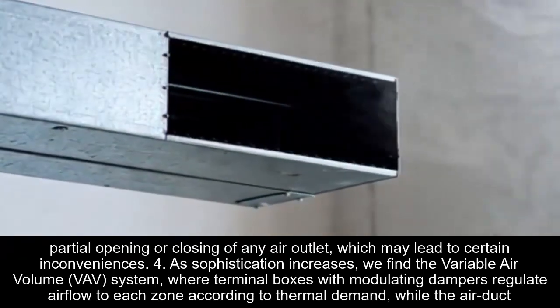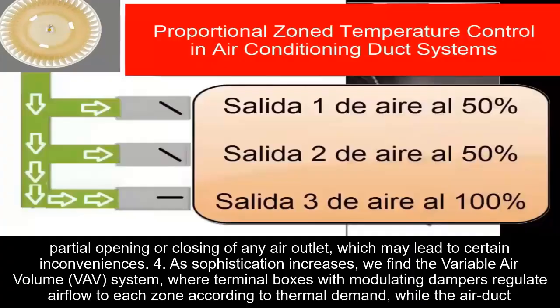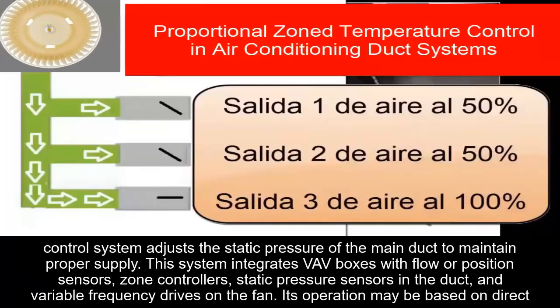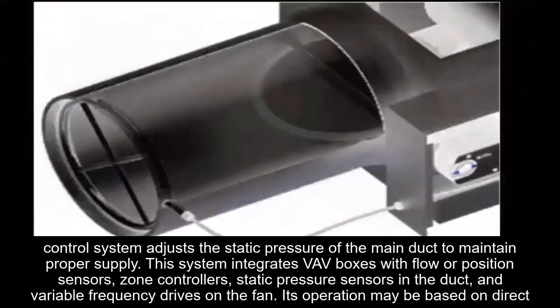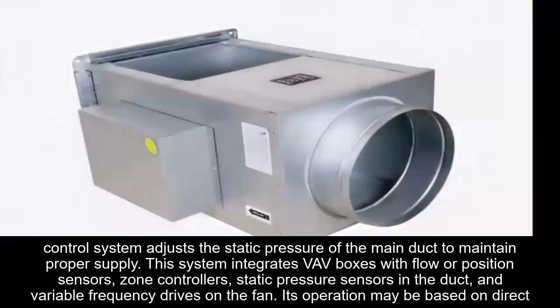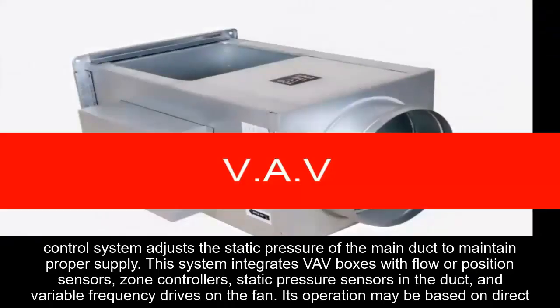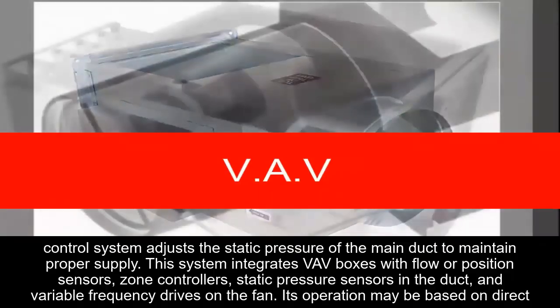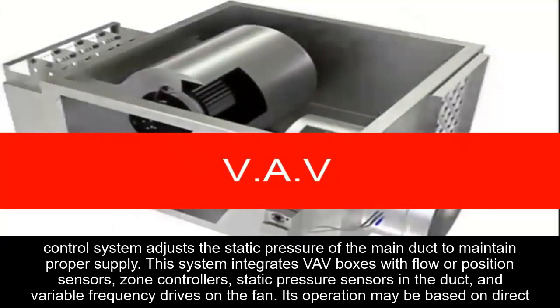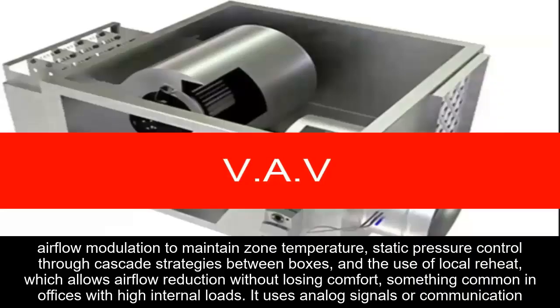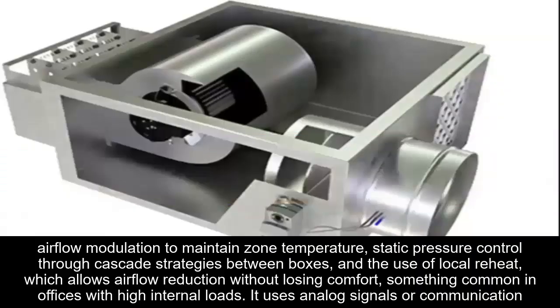As sophistication increases, we find the variable air volume VAV system, where terminal boxes with modulating dampers regulate airflow to each zone according to thermal demand, while the air duct control system adjusts the static pressure of the main duct to maintain proper supply. This system integrates VAV boxes with flow or position sensors, zone controllers, static pressure sensors in the duct, and variable frequency drives on the fan.